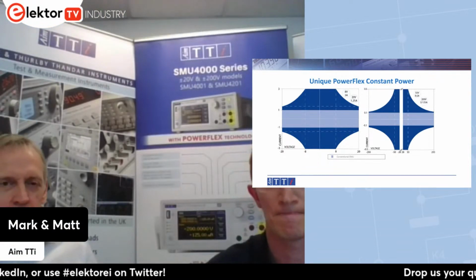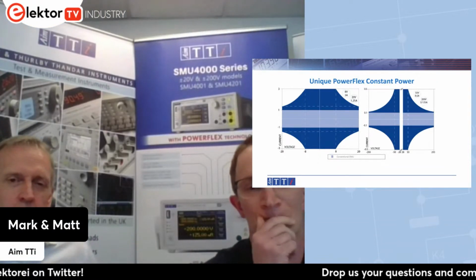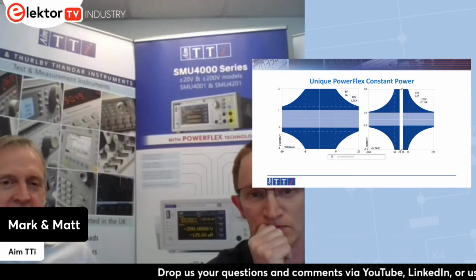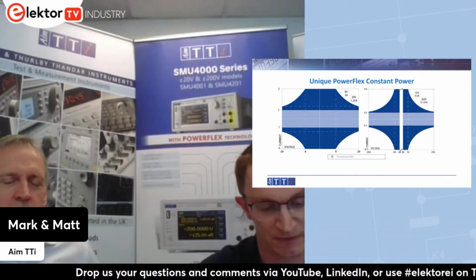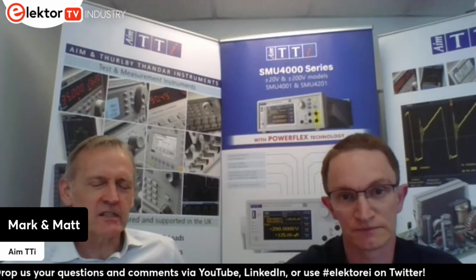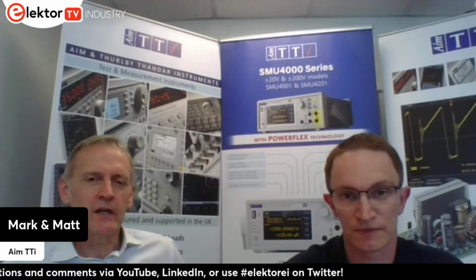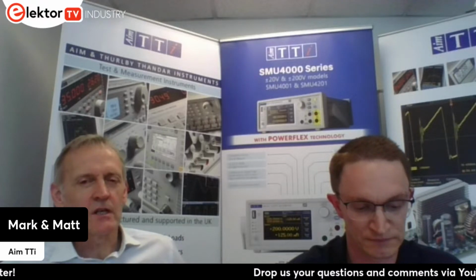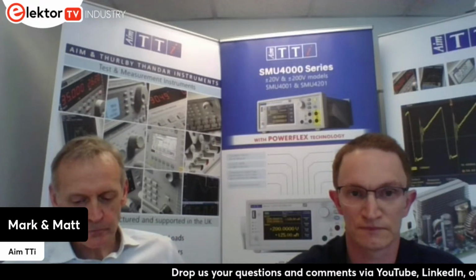Well, to make it easier to set up on the SMU 4000, we do have predefined easy setup modes, which enable you to go through, presently I think it's 8 setups, for defining the outline parameters for any setup. The customer can then set their own limits and their own levels within that setup.